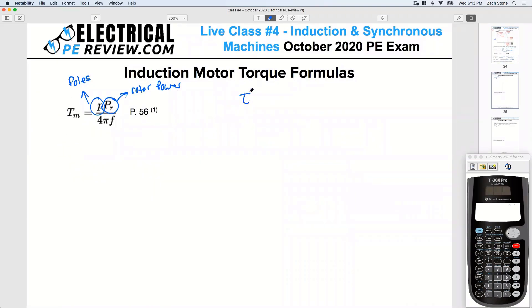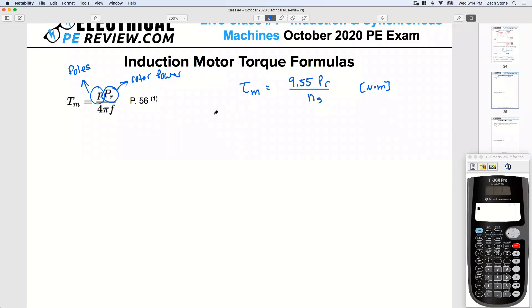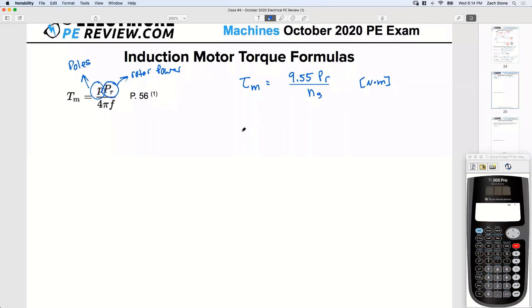The formula we're most used to working with is: mechanical torque equals about 9.55 times rotor power divided by synchronous speed, and the units are newton-meters. These two formulas on pages 52 and 56 are the same — let's prove it. First, let's define synchronous speed from frequency and poles. It's a simple formula — plug in a couple values and you get 1800 RPM.